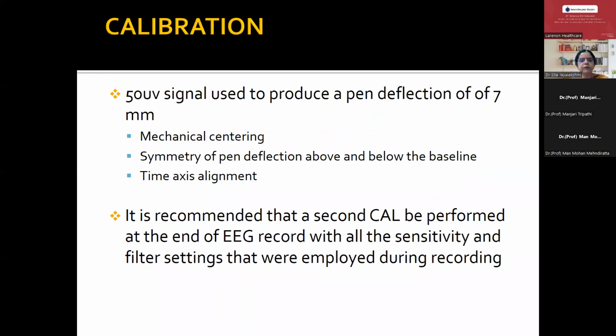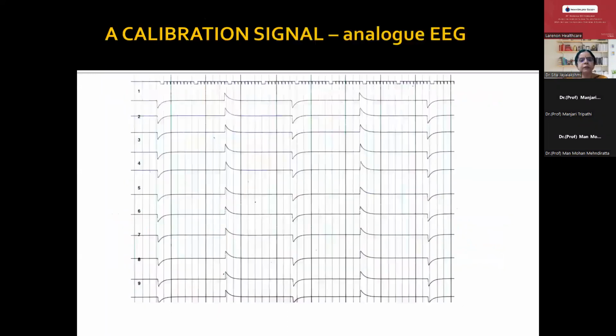Calibration has 2 parts. One is mechanical calibration, the second is biocalibration. Mechanical calibration is normally done by the technologists before starting, by giving a 50 microvolt signal from the machine, which will produce a pen deflection of around 7 millimeters. This was mainly to make sure that in the analog machine all the pens are aligned properly, whereas in a digital machine, we look at the symmetry of the deflections. It is recommended that a second calibration be performed at the end of the EEG recording to make sure that during those 40 minutes of recording, the alignment is still maintained.